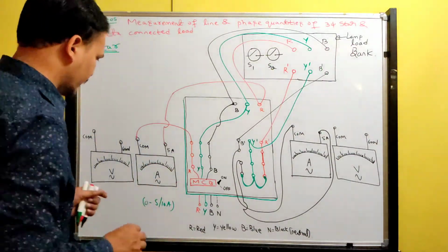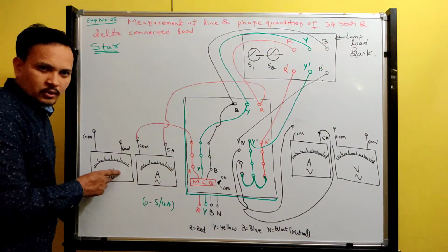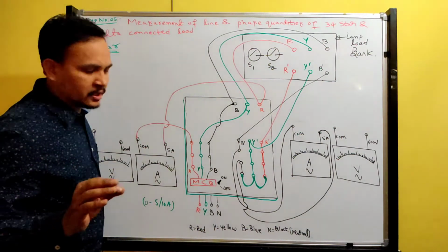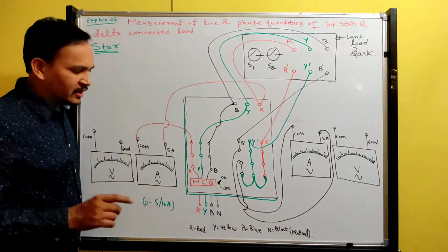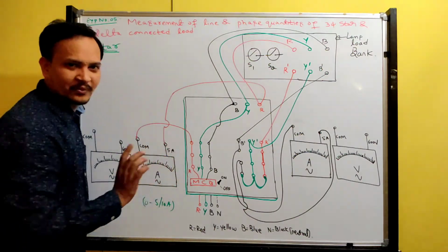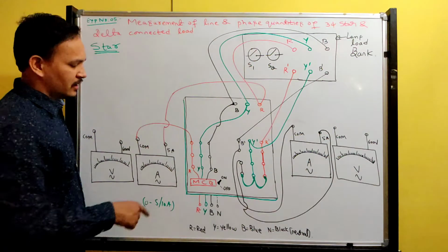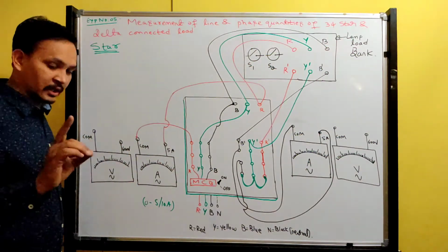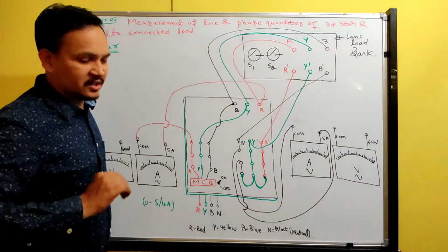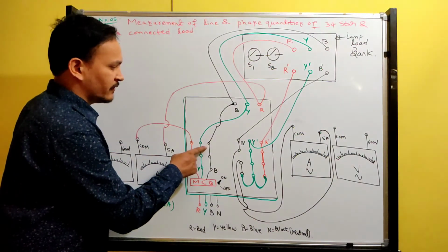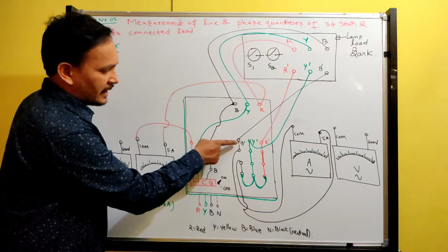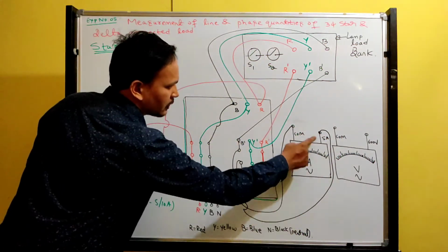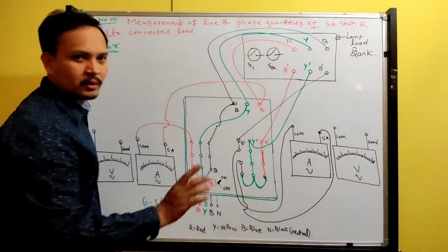Now think about voltmeter. What is this voltmeter? Line voltage. See, precaution is, am I connected ammeter between R and Y? No, I connected in one only. If I taken with R, it is ended with R only. That is the safety you should take while connecting the ammeters. So B phase, if I connect ammeter in B dash, again I ended with same terminal. Look at here, started with B dash and another is connected to B dash only.